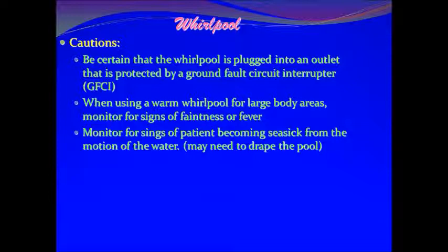Cautions when using whirlpool: you need to be certain that the whirlpool is plugged into an outlet that's protected by a ground fault circuit interrupter, or a GFCI. This is to assure that there will not be a shock from the electric motor to the patient or to the therapist. When using a warm whirlpool for large body areas, you need to monitor for signs of faintness or fever within your patient, making sure that they can tolerate the increased heating effect of the water. You also need to monitor for signs of patients becoming seasick from the motion of the water. And in some cases, although these are very rare, you may need to actually drape the pool so that the patient doesn't physically see the water moving and become somewhat seasick.